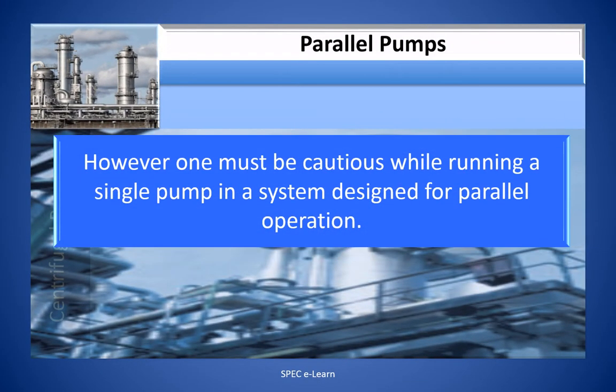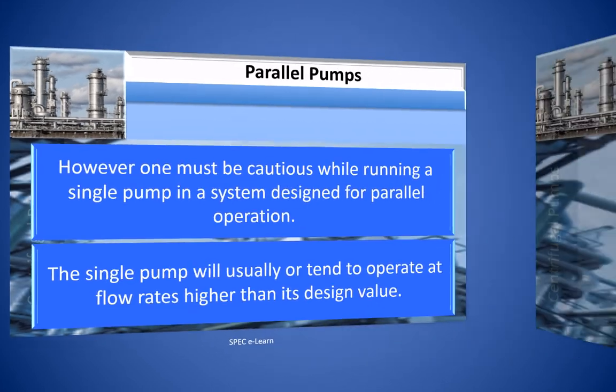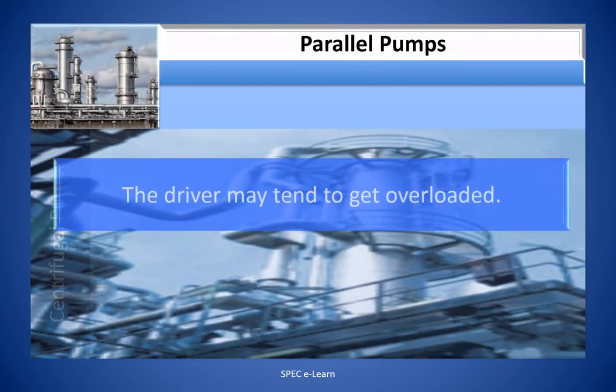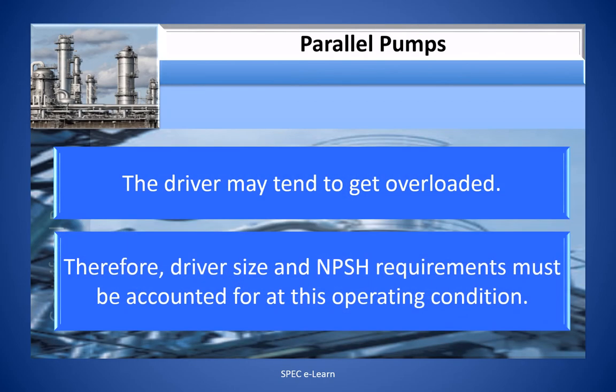However, one must be cautious while running single pump in a system designed for parallel operation. The single pump will usually or tend to operate at flow rates higher than its design value. The driver may tend to get overloaded. Therefore, the driver size and NPSH requirement must be accounted for at this operating condition.